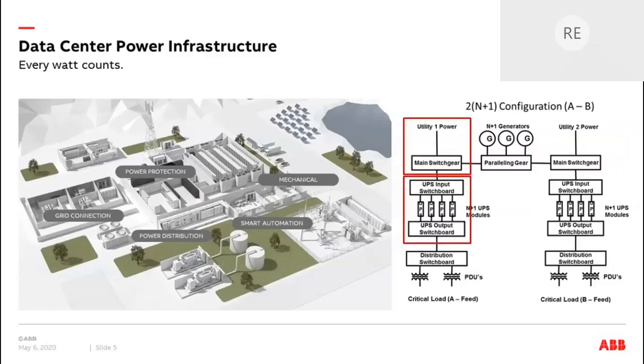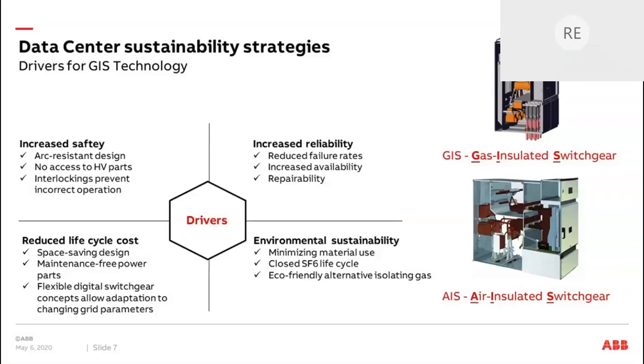So with GIS and UPS, we are on the one hand looking on the utility side. So medium voltage switchgears are basically used on both sides of a transformer and in various locations in the medium voltage network. And in the second part of the session, we are going to talk about the UPS on the switchboards. So during the session, I'm going to use a couple of abbreviations which I would like to explain. GIS stands for gas-insulated switchgear, and AIS stands for air-insulated switchgears.